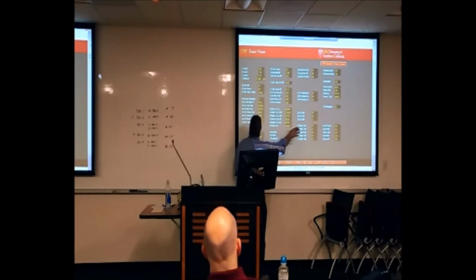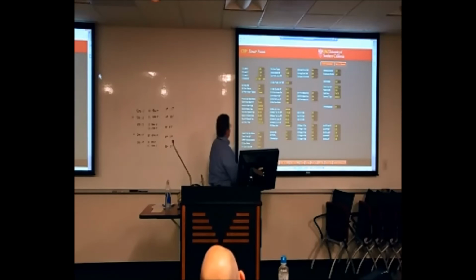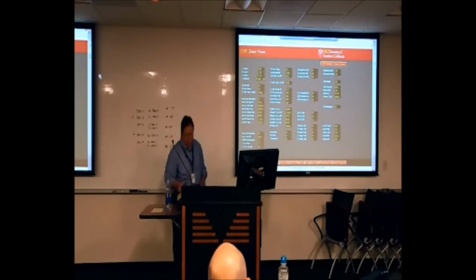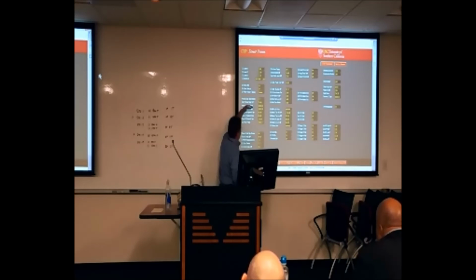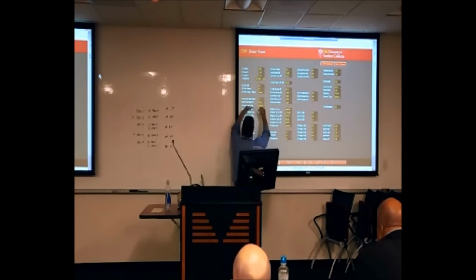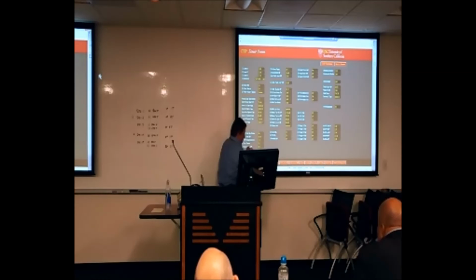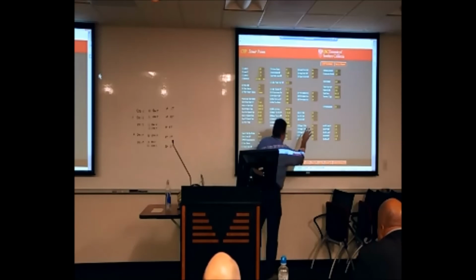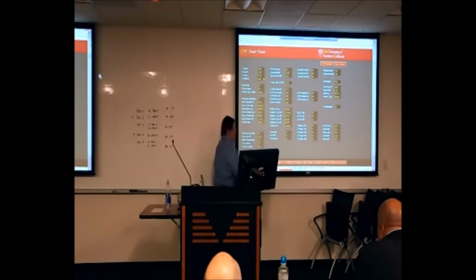When we're in this mode, we have min and max caps. The sequence specified, and this has to do with the staging as well, that in your particular stage they wanted to maintain at least the minimum GPM going through these towers. So it's going to control either off of this delta P control, or it's going to adhere to these minimum GPM or maximum GPM requirements. So it's still going to be bracketed by the high GPM cap and the low GPM cap reflected right here. As the chillers stage up, these numbers are going to change. Those are the GPM caps that it needs to operate between, while it's also operating between those DP constraints that are driven by the delta T requirements.